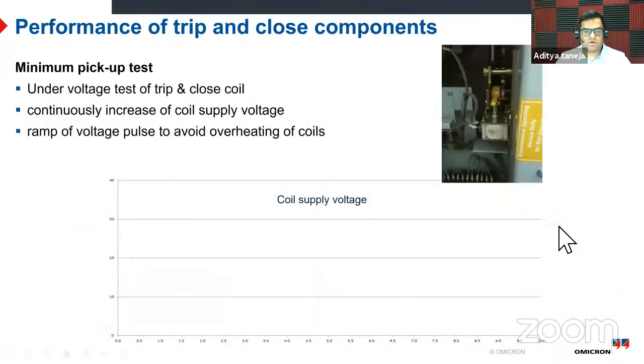The other test, again done on the coil, as I said, to check the force which is needed for the breaker to operate, is the minimum pickup test. This is a different test. This is not an under voltage test. Here we are not checking the time. We are only checking the force needed for the breaker coils to operate.